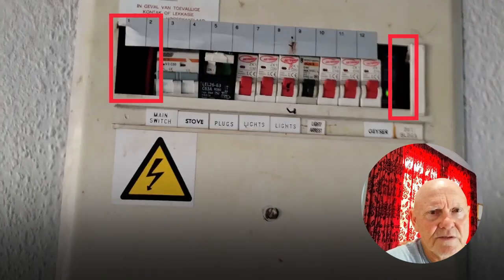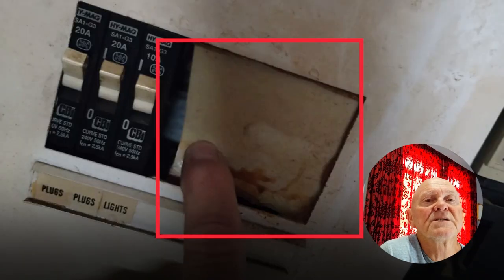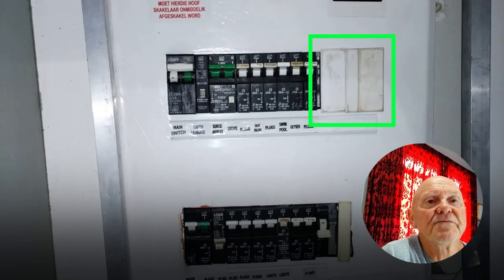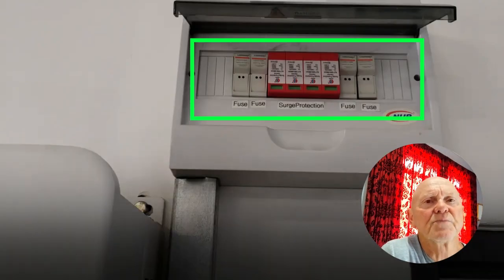There are no open gaps that lead to live parts. This is one of the most common problems I see. Open spaces where you can literally touch something live if you stick a finger or a tool in there. And people fix it with a piece of plastic, PVC or tape. That's not a real fix. Those openings must be properly closed in a way that only opens with a tool. There are specifically designed distribution board blanks to be used in the open gaps. The circuit breakers must also fit properly. In other words, they have to fit into the slots designed for that specific distribution board. The inside backplate in the distribution board is adjustable, so the faceplate can fit properly and correctly. If a child can reach it, it's a problem, a big problem.